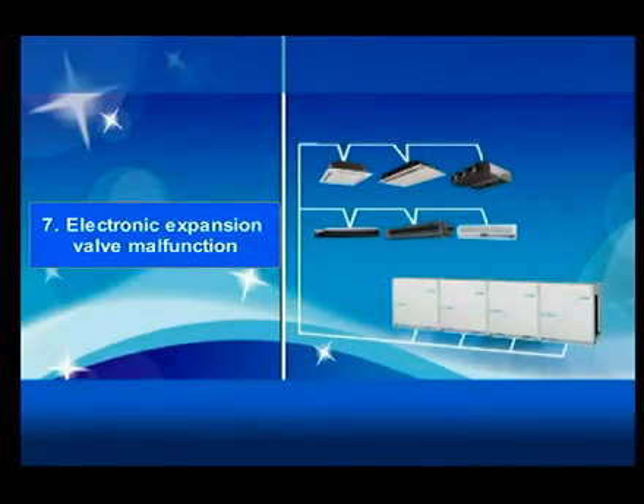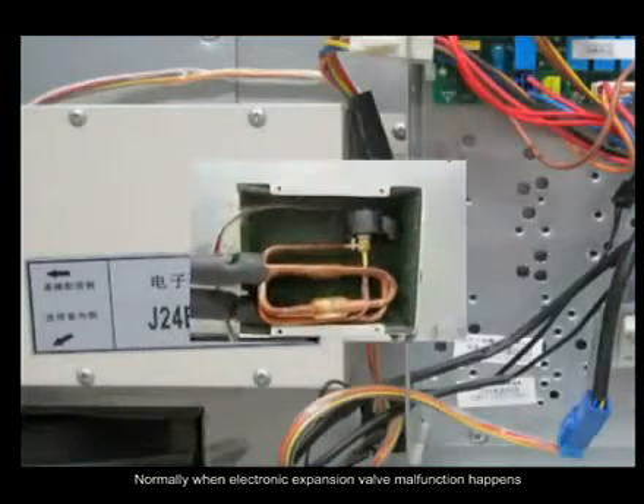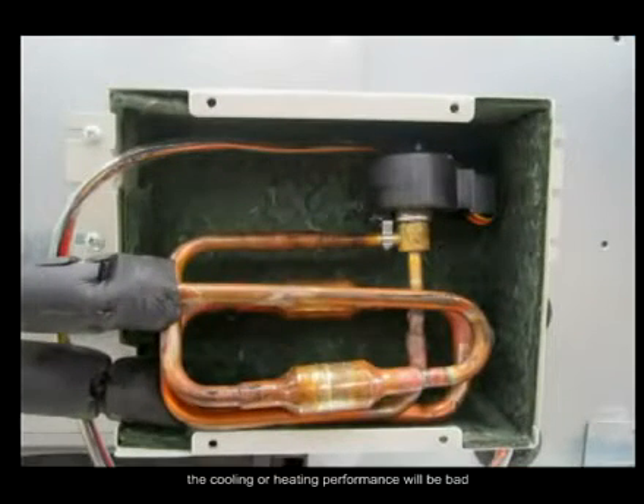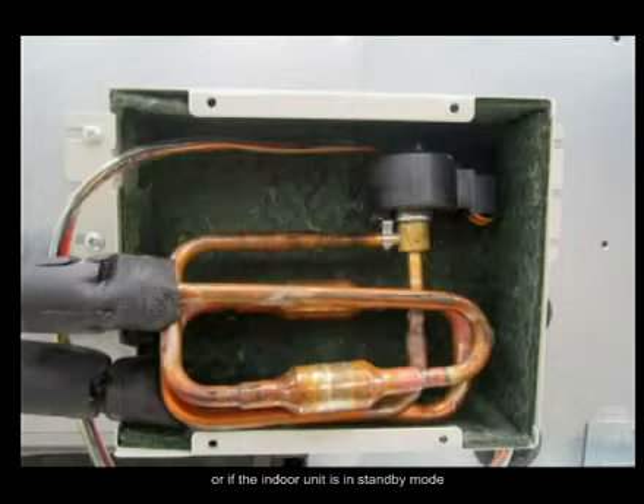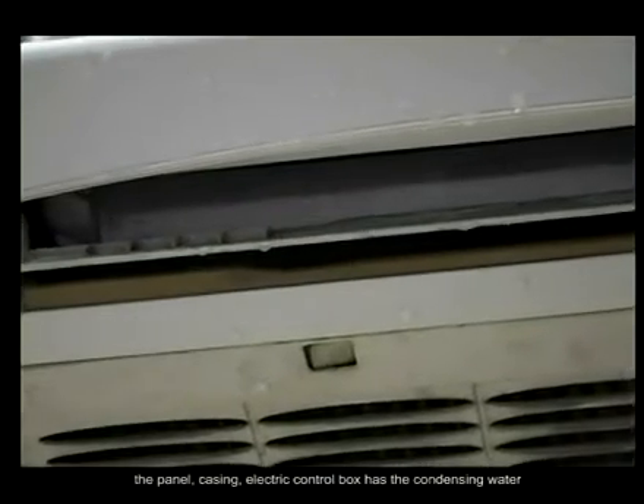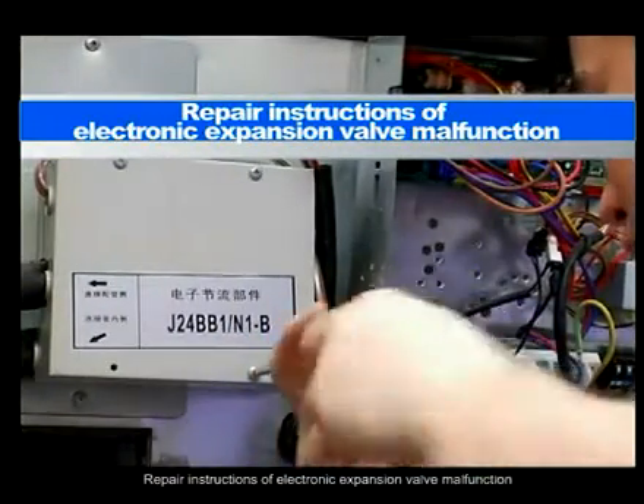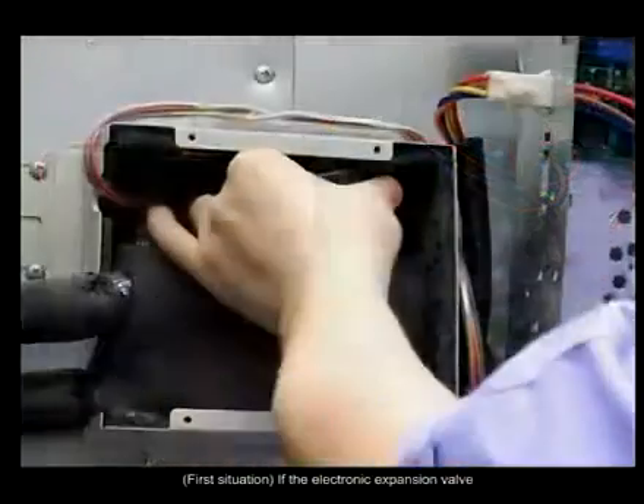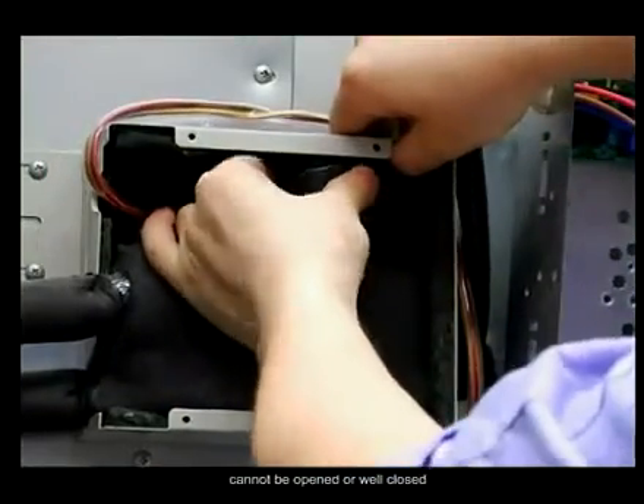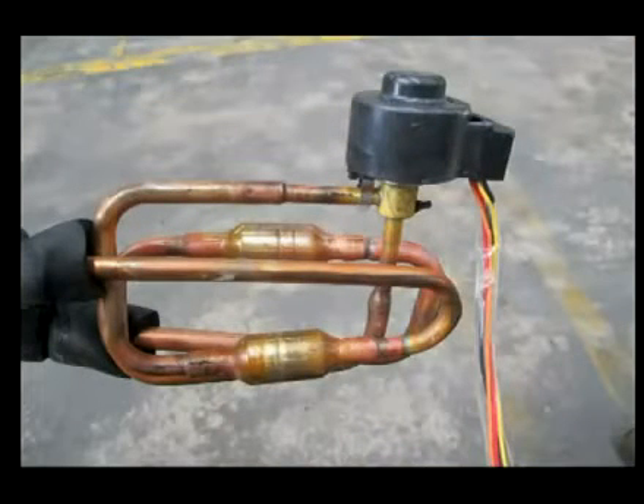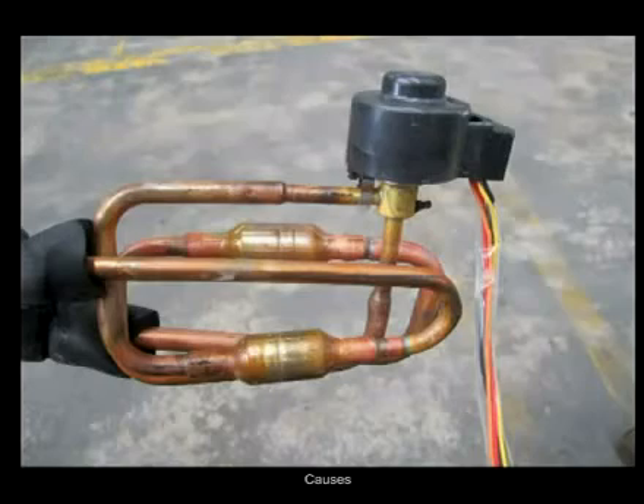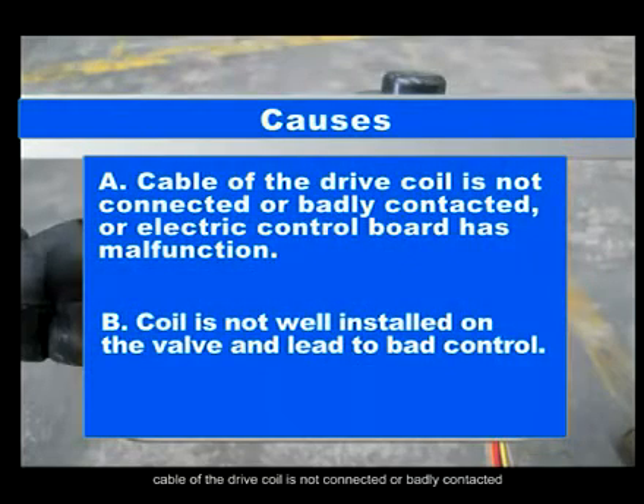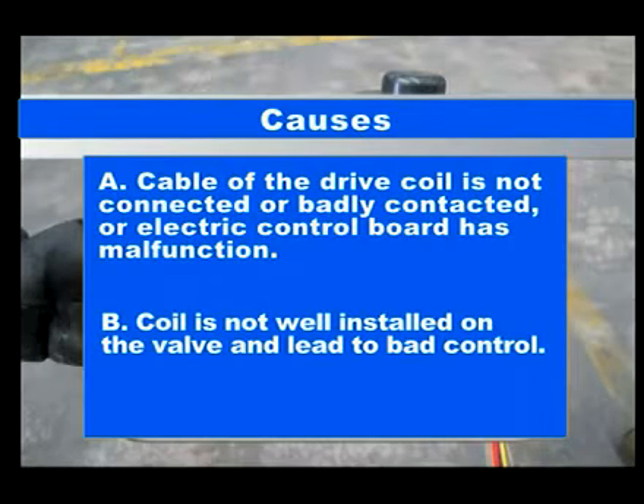Electronic expansion valve malfunction. Normally, when electronic expansion valve malfunction happens, the cooling or heating performance will be bad, or if the indoor unit is in standby mode, the panel, casing and electronic control box have condensing water. Repair instructions of electronic expansion valve malfunction. First situation. If the electronic expansion valve cannot be opened or well closed, the valve has no sound of action or the sound is smaller. Causes. The cable of the drive coil is not connected or badly connected, or the electric control board has a malfunction. The coil is not well installed on the valve, leading to bad control.